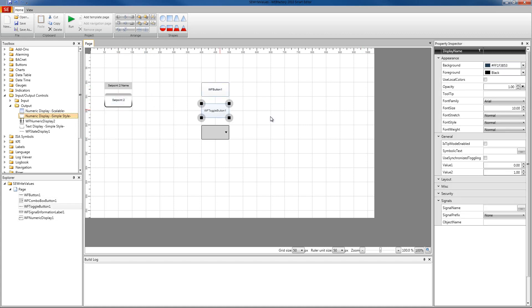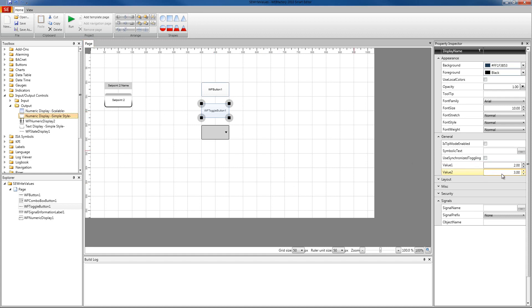We're going to select the toggle button now. As you can see, the toggle button in the general properties has two different values — this is because this button is going to toggle between these two values. So we're going to have the first value two and the second value three. Whenever we press this button once, the first value will be written to our signal, to our PLC. If we press it the second time, the value three will be written to our PLC. And we're going to link it to the same set point two signal.